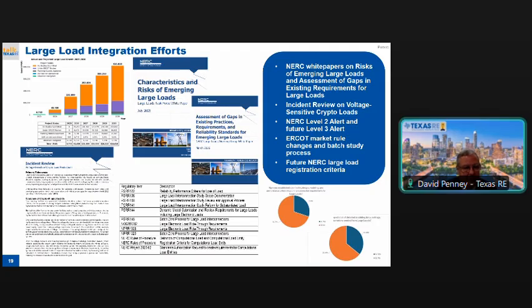There was a lot of good work between the various NERC working groups and the ERCOT working groups. A couple of major reports and white papers came out from the NERC groups, related to emerging characteristics and risks of emerging large loads, as well as an assessment of gaps in existing practices. At the same time, there was a combined effort between NERC, Texas RE, and ERCOT to look at voltage-sensitive load loss events within ERCOT. This was a sister companion report to the initial report from the Dominion event last year, and it highlighted many specific issues related to Bitcoin and crypto miners.